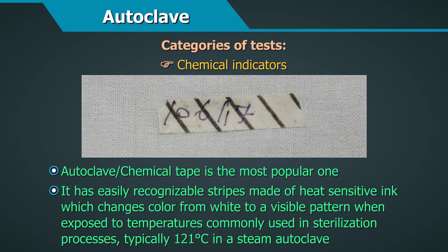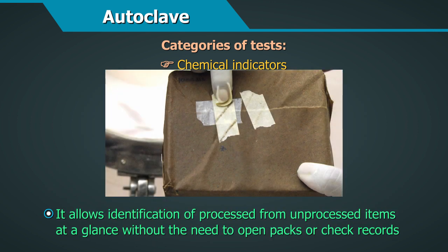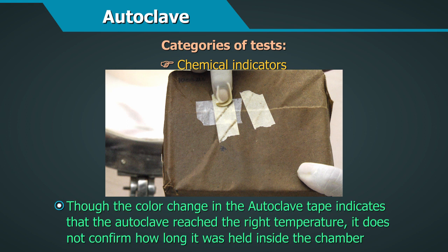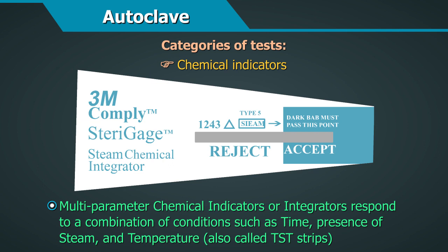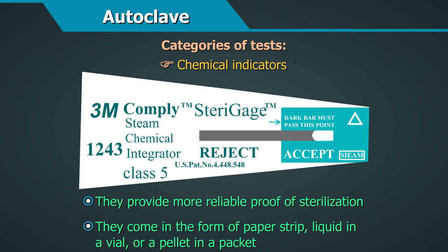Autoclave chemical tape is the most popular indicator. It has recognisable stripes of heat-sensitive ink which change colour from white to a visible pattern when exposed to temperatures typically used in sterilization, such as 121°C in a steam autoclave. It allows identification of processed from unprocessed items at a glance without opening packs. However, the colour change only indicates the autoclave reached the right temperature — it does not confirm how long the item was held inside. Multi-parameter chemical indicators, or integrators, also called TST strips, respond to a combination of time, presence of steam, and temperature, providing more reliable proof of sterilization, and come as a paper strip, liquid in a vial, or pellet in a packet.